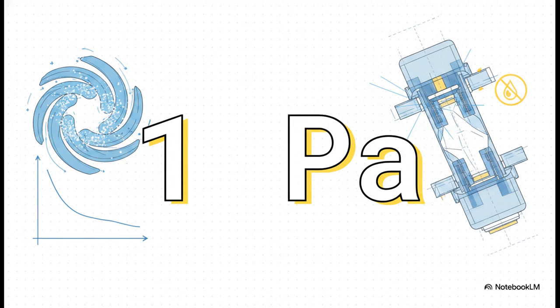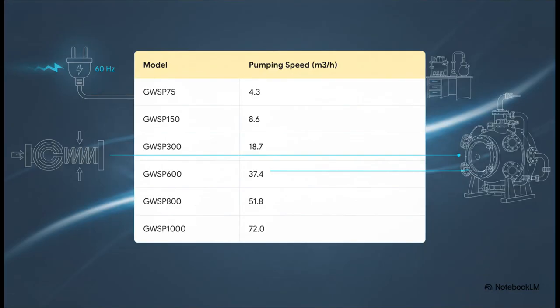on those scroll plates. Looking across the 7 different models in this series, you get a really wide band of capability. Running on a 60 Hz power supply, the pumping speeds start at 4.3 cubic meters per hour for the compact 75 model and scale all the way up to a massive 72 cubic meters per hour for the 1000. So whether you're just outfitting a small analytical benchtop instrument or you need to exhaust a massive industrial chamber, there's an optimal capacity here for sure.